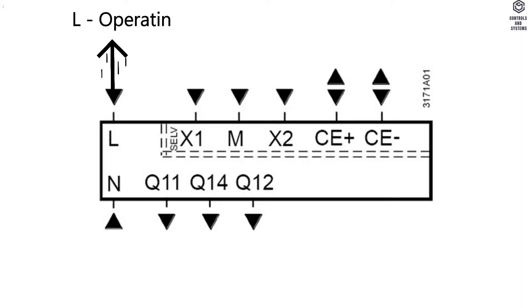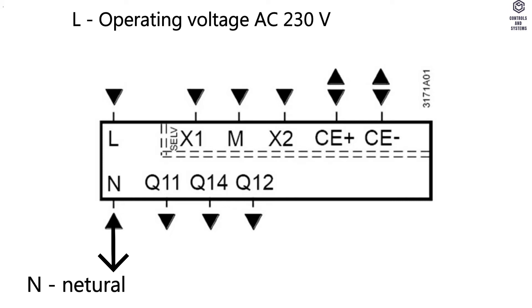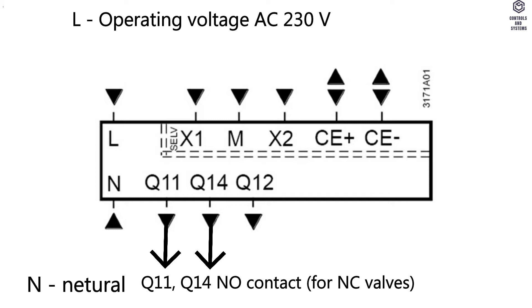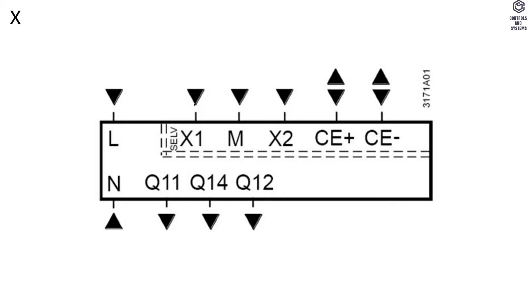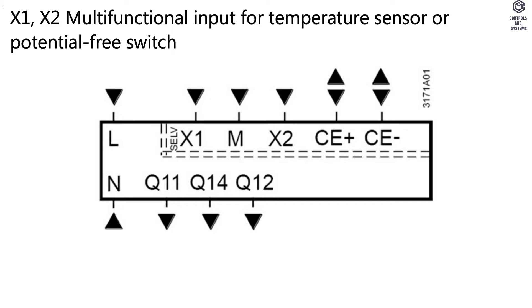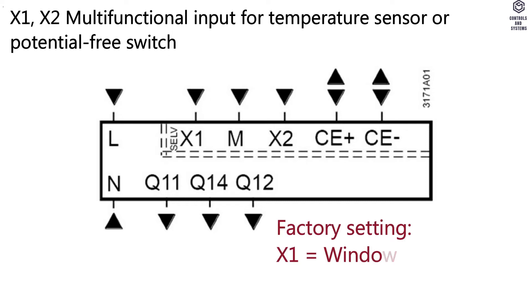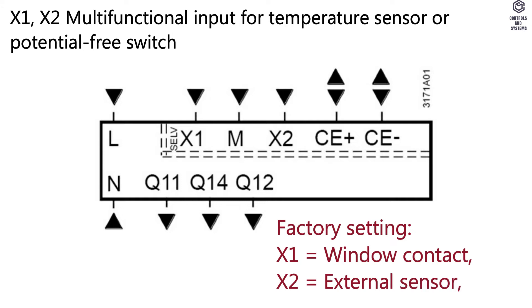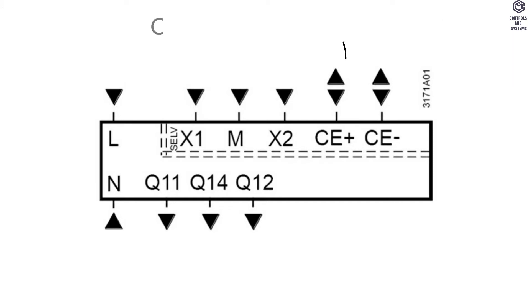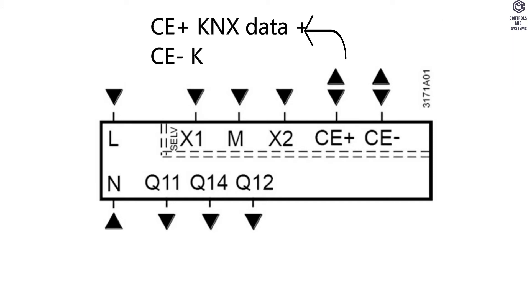Connection Terminals: L terminal — operating voltage AC 230V. N terminal — neutral. Q11 and Q14 terminal — NO contact for NC valves. X1 and X2 terminal — multifunctional input for temperature sensor or potential-free switch. Factory setting: X1 = window contact, X2 = external sensor. M terminal — measuring neutral for sensor and switch. CE+ terminal — KNX data plus. CE− terminal — KNX data minus.